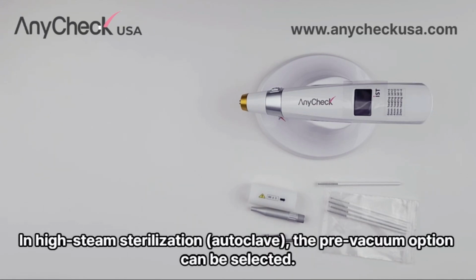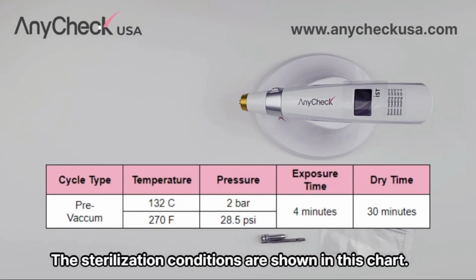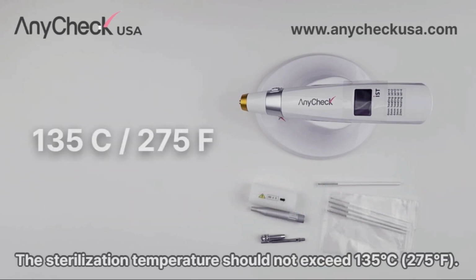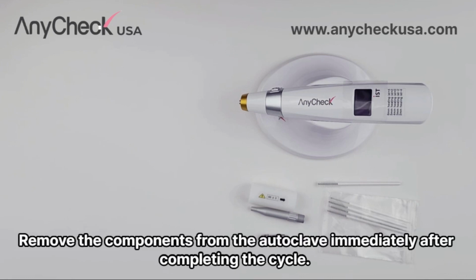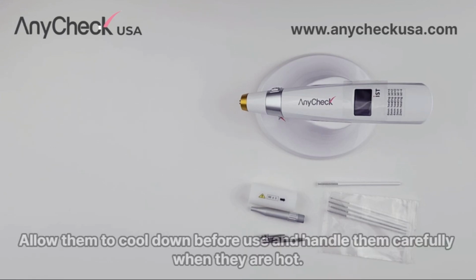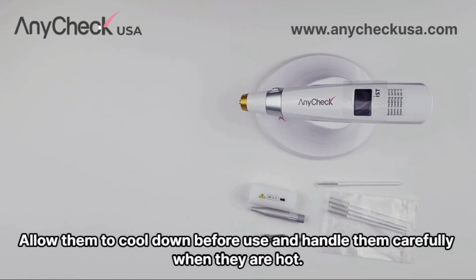In high steam sterilization, the pre-vacuum option can be selected. The sterilization conditions are shown in this chart. The sterilization temperature should not exceed 135 Celsius or 275 Fahrenheit. Remove the components from the autoclave immediately after completing the cycle. Allow them to cool down before use and handle them carefully when they're hot.